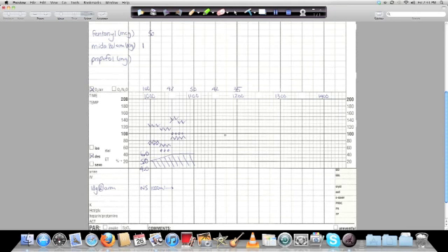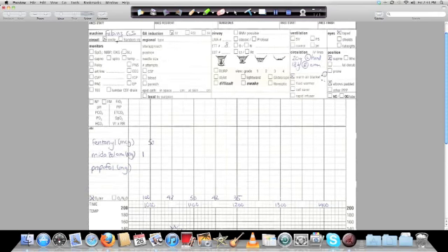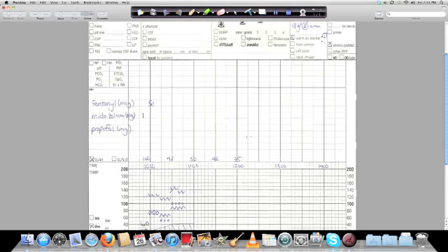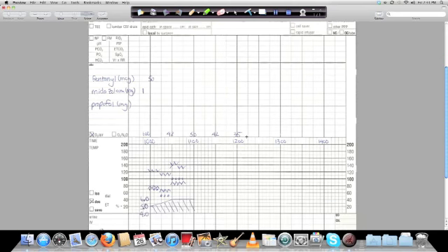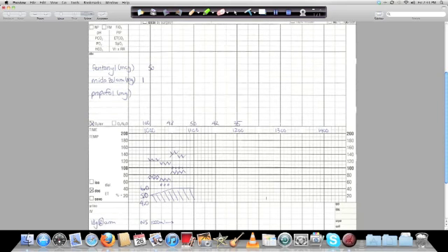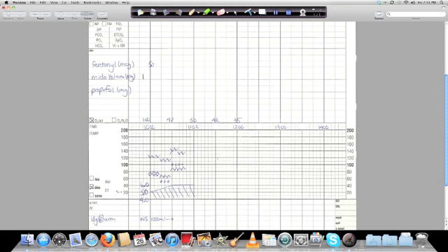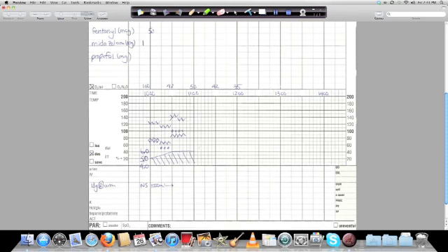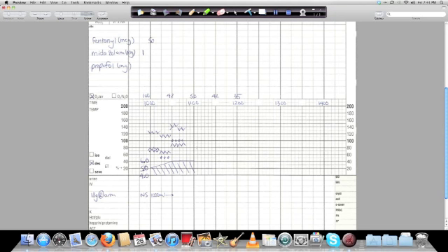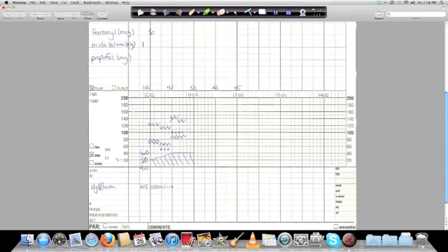Don't be concerned with making sure you check every 5 minutes. The machine itself, our friend Fabius GS here, will actually tabulate every 5 minutes the values for blood pressure and for heart rate and for pulse oximetry, which you would track up here. And so, once you get the operation underway and everything's running smoothly, you can take a second to jot down your notes. And that's usually the practice that's done in the operating room. Everything gets started, and then you pull up the table on the anesthetic machine and tabulate everything as you go. And then once everything's settled, you have a bit more time.